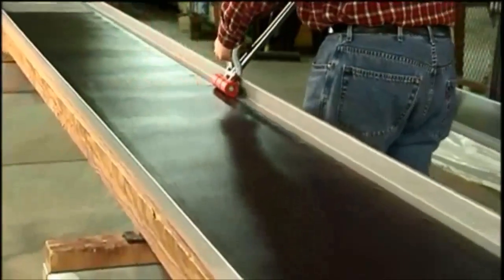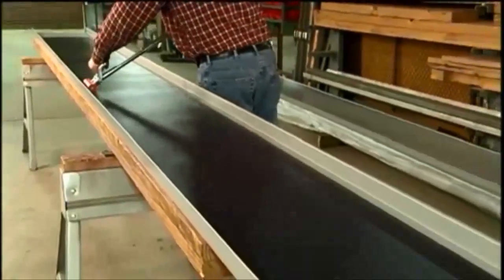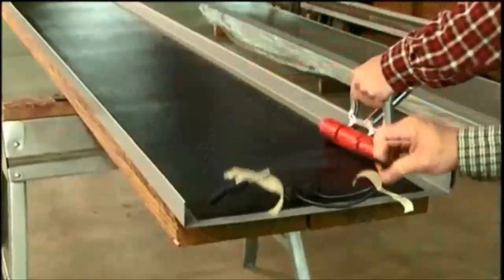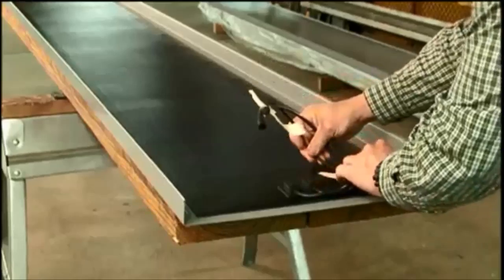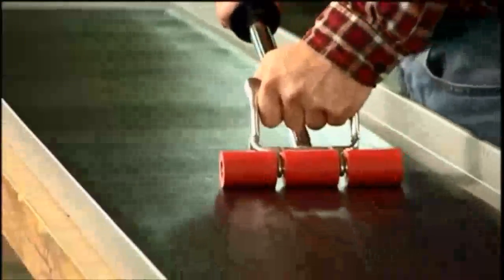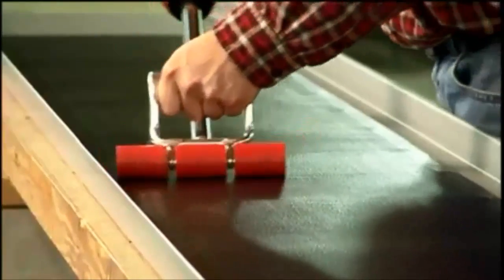Roller pressure must be applied to the entire surface of the laminate, including the entire length of all panel edges. Adhesion and rolling of the upper edge, near the wires, is especially important since this will often be the edge most exposed to the weather. The adhesive is pressure sensitive and it will reach its full bond strength to the panel after about 24 hours.